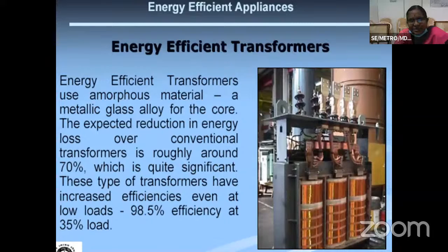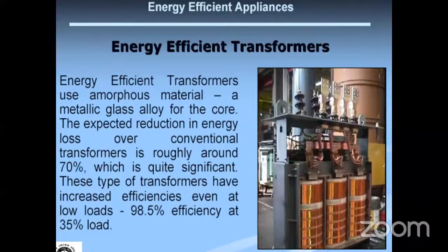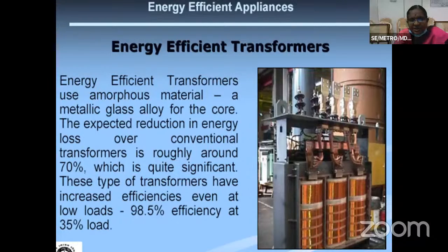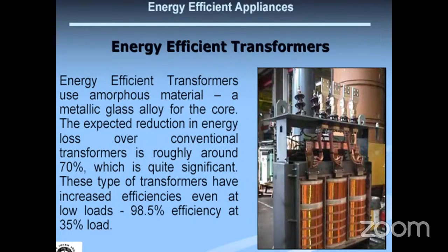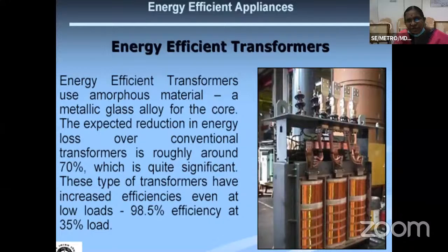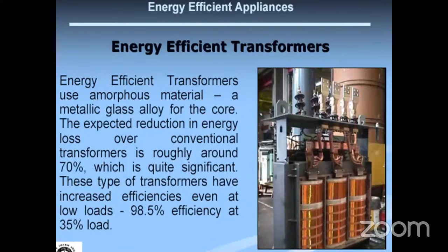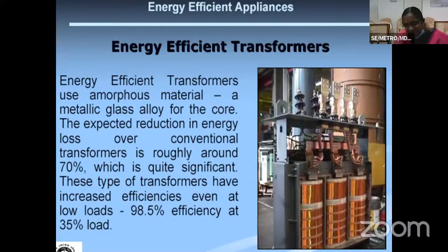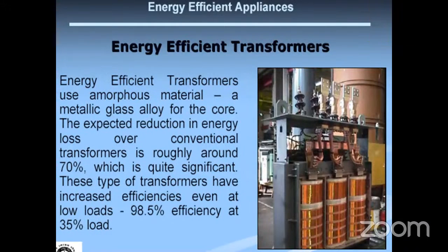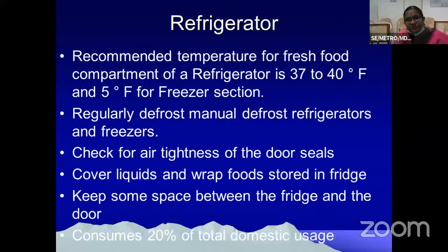Energy efficient transformers use an amorphous material, a metallic glass alloy, for the core. The expected reduction in energy loss over the conventional transformers is roughly around 70%, which is quite significant. These types of transformers have increased efficiency even at low loads, 98.5% efficiency at 35% load. So use amorphous material energy efficient transformers instead of the normal iron core transformers. We also started this type of transformers. This is in the domestic sector, the opportunity to save energy in the refrigerator.